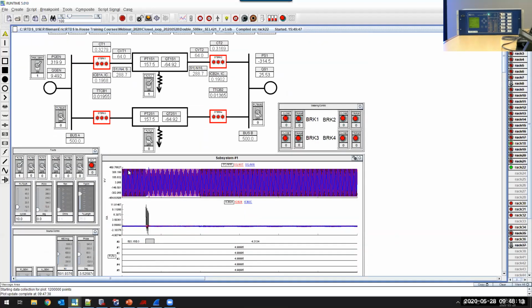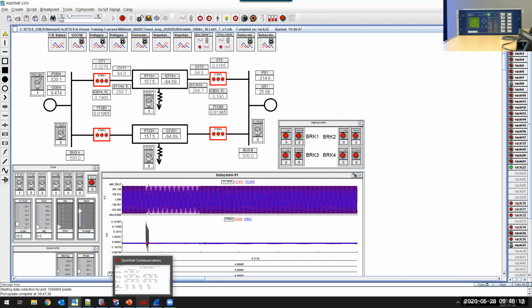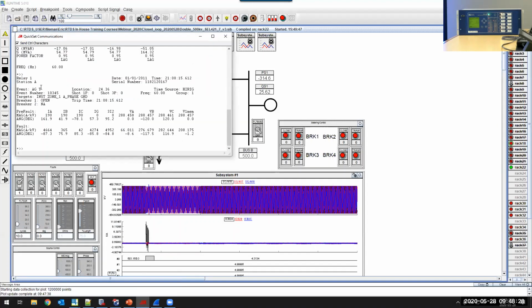Now let's have a look at the result from the relay. You can see the results from the front panel of the relay, but the hyperterminal also updated the result here. The event is detected as AG trip, which means A phase to ground trip, and the location is 24.36. Remembering the ideal location is 24.25. This tells us the relay is synchronized to a high resolution IRIG, which comes from the GTSync card. So it's a zone 1 A phase to ground fault. Then you have the pre-fault measurements here, and also the measurements at the fault.